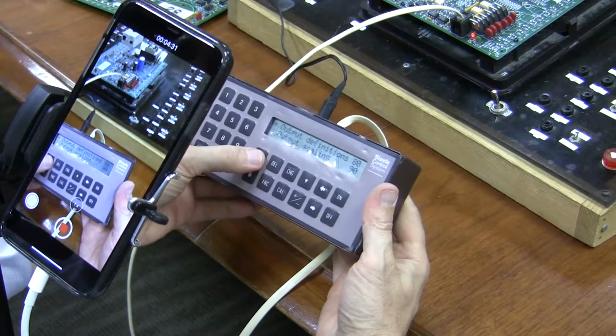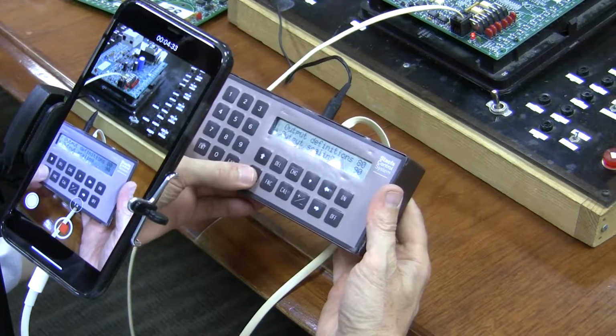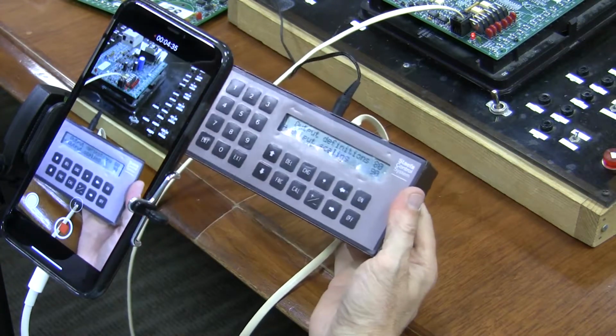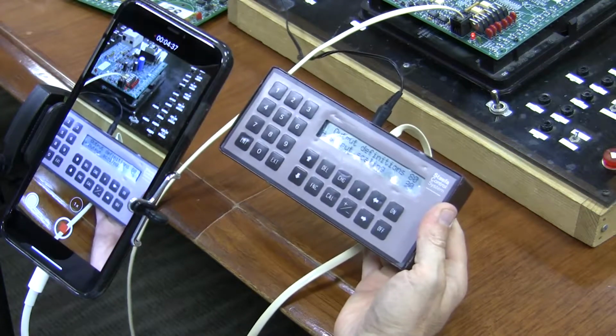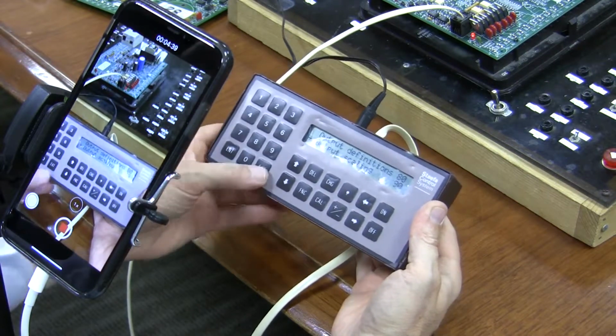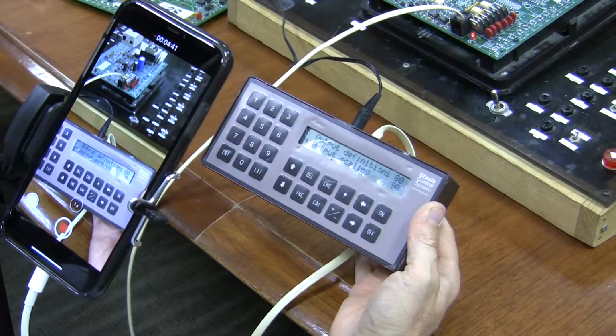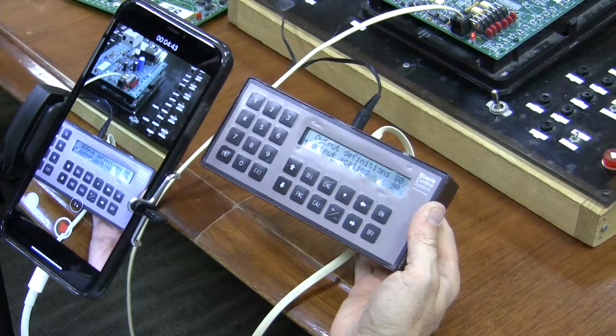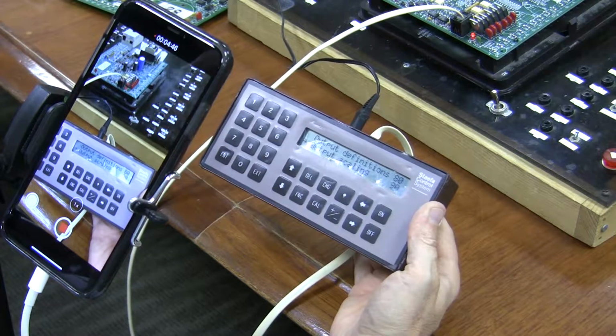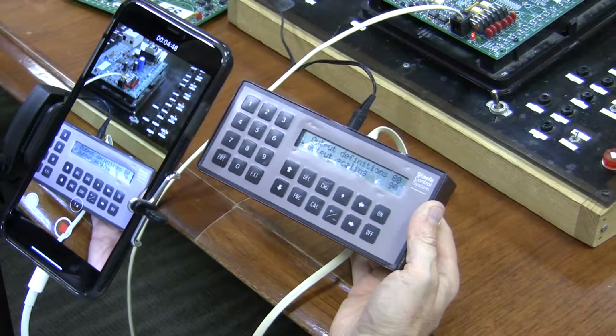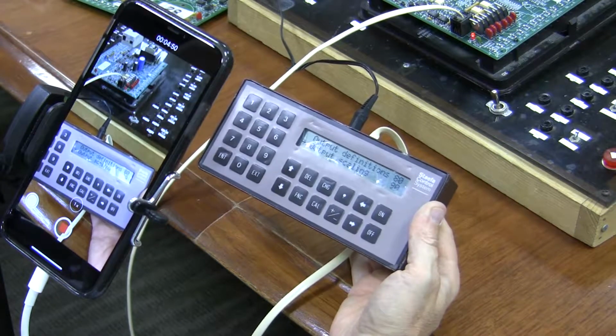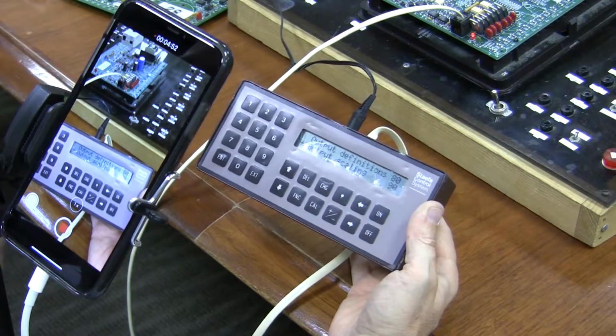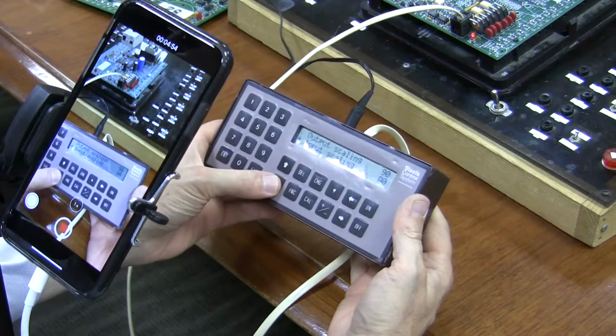So that's what the output definitions are. Output scaling allows me to scale the outputs of the card. For example, if the valve is a 0 to 5 volt valve but this puts out 0 to 10 volts, I could just scale it to 50%. That's what output scaling is all about.